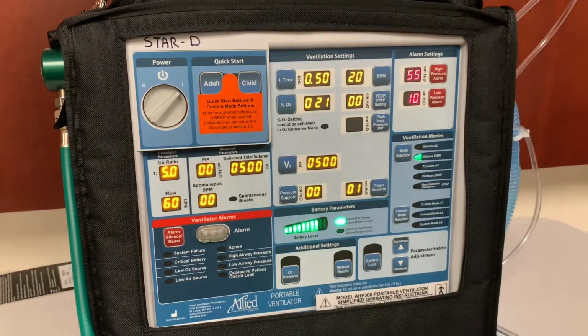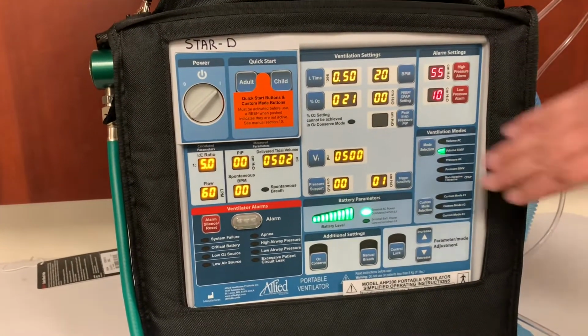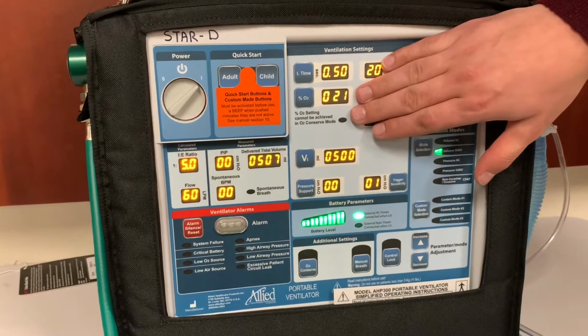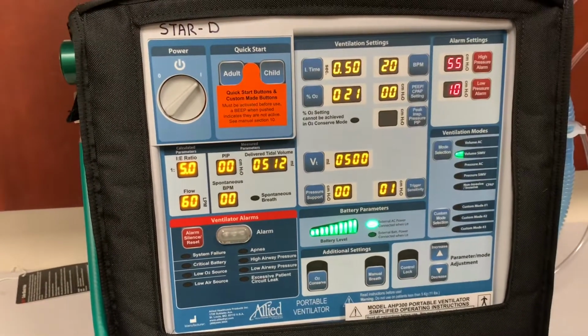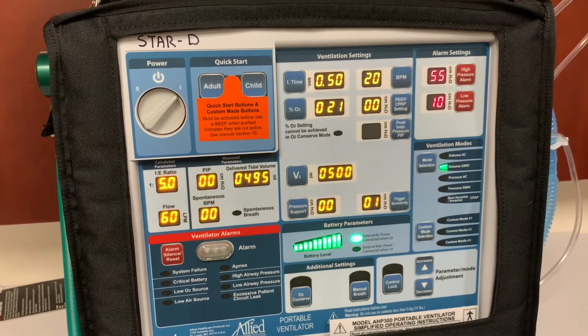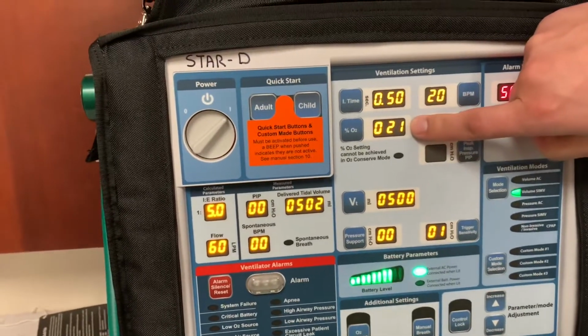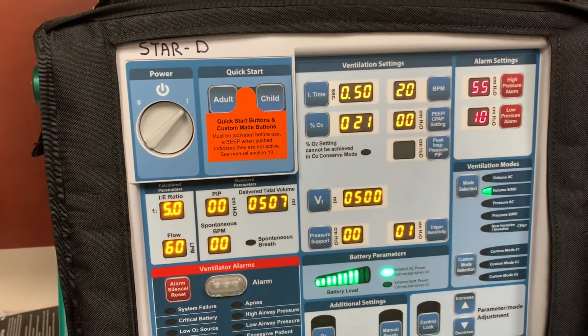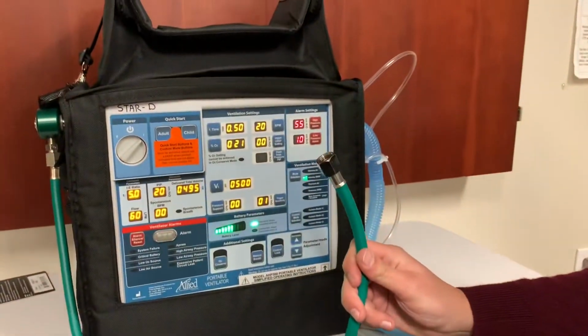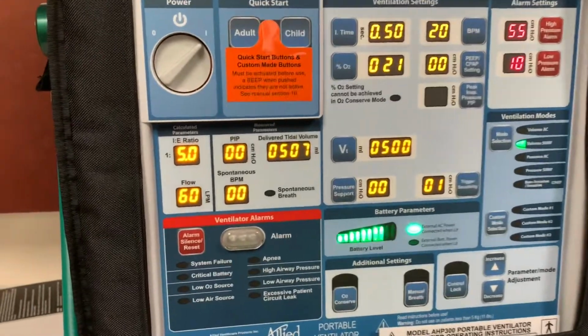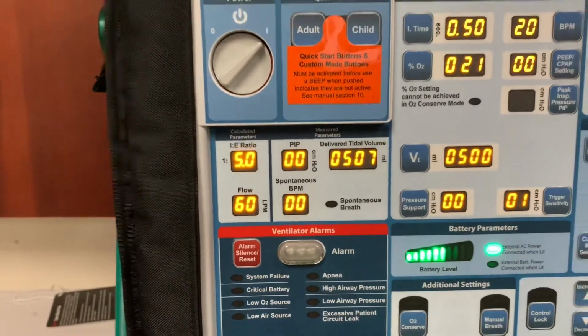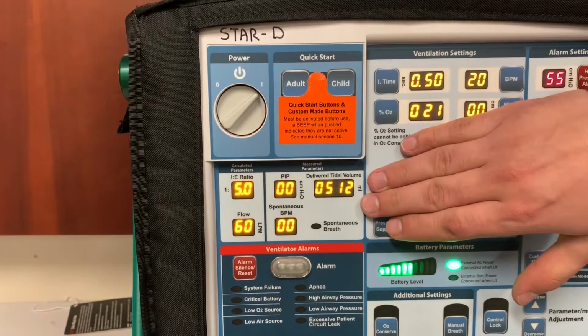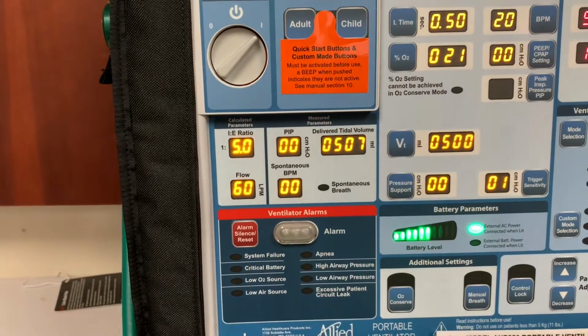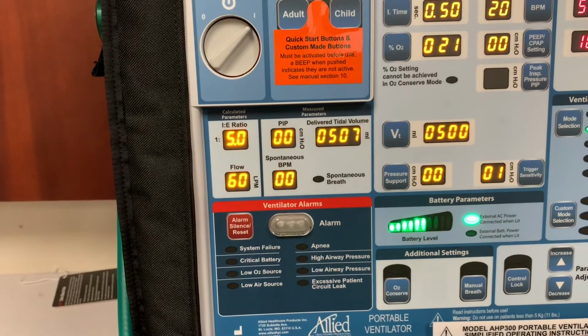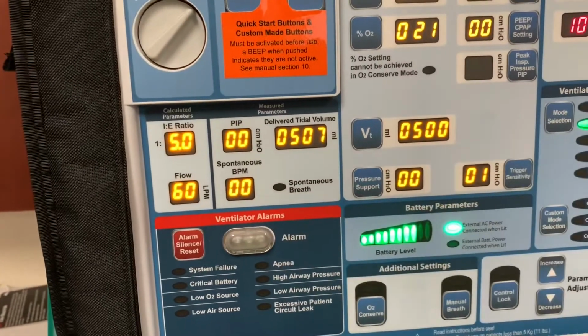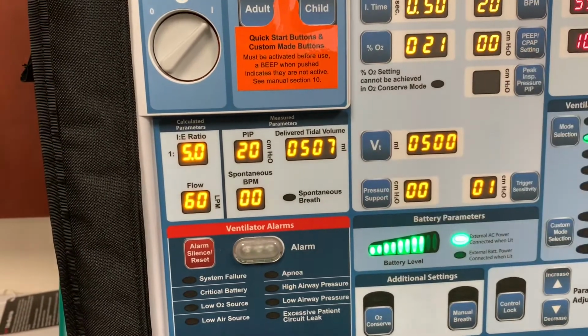The AHP 300 has a built-in compressor, hence why you don't actually have to be connected to oxygen in order to ventilate. However, it will only ventilate atmospheric air at that time, which has an oxygen percentage of 21%. If you want to be able to increase your oxygen percentage above 21, you must have it connected to oxygen. You can also get real-time feedback on what's actually being delivered to your patient over here on the left-hand side, just below the power. As you can see, since we're not actually connected to a real patient, it is showing 0 spontaneous breaths per minute. You can see that it's delivering 507 ml of tidal volume.